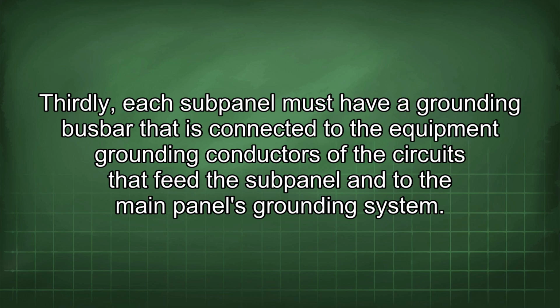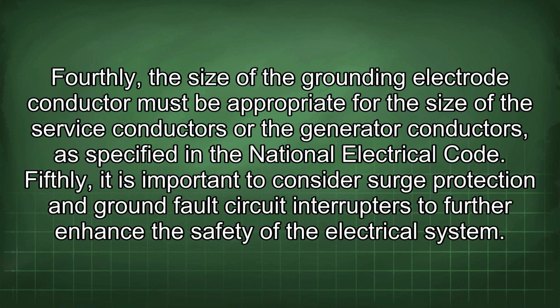Thirdly, each subpanel must have a grounding busbar that is connected to the equipment grounding conductors of the circuits that feed the subpanel and to the main panel's grounding system. Fourthly, the size of the grounding electrode conductor must be appropriate for the size of the service conductors or the generator conductors, as specified in the National Electrical Code.